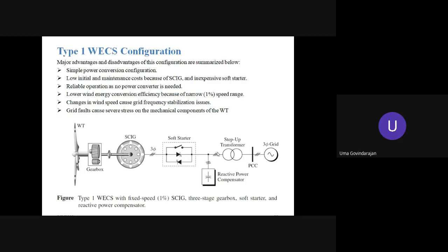Because apart from the synchronous speed, it requires a gearbox. The SCIG will work as a generator for speeds greater than the synchronous speed. Suppose it is a 1500 RPM machine, we need to operate it at a speed higher than 1500. Below the synchronous speed, generation is not possible, and above the synchronous speed also, wide speed variation is not allowed.